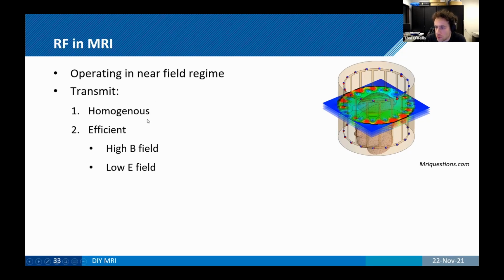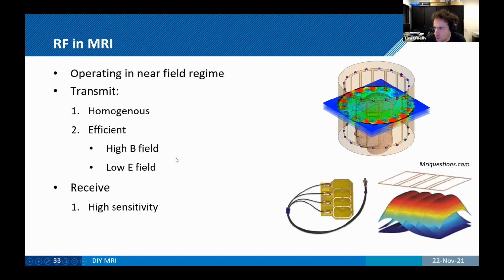On the transmit coils, we want that field to be very homogeneous to prevent any shading in our images because of imperfect excitation angles, as well as changes in image contrast. And you want them to be efficient, and efficient in two ways. You want a high magnetic field per unit current, because then you can give shorter RF pulses to get the same excitation. But you also want your electric fields to be very, very low. So it's kind of a two-parter there.